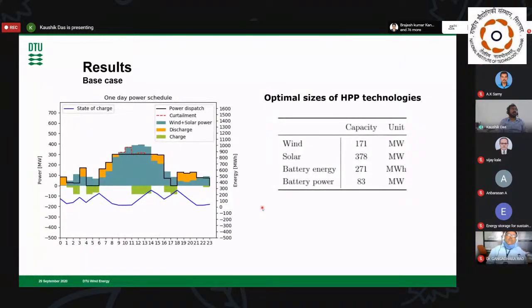For the optimal case, we found that wind should be 171 megawatts and solar 378 megawatts for this 300 megawatt connection, with a 271 megawatt-hour battery, meaning 83 megawatts, so around a 3-hour capacity rate of battery storage. This is lithium-ion battery we are looking at here.